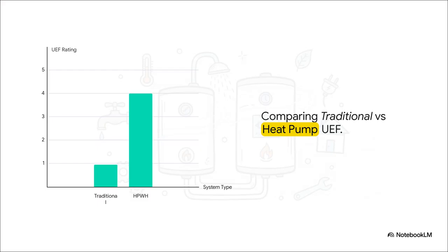Okay, to make that strategic choice, we have to talk about the Uniform Energy Factor, or UEF. It's the gold standard for measuring efficiency, and it brilliantly illustrates the sheer power of multipliers. So traditional electric resistance tanks maxed out at a UEF of about 0.95, meaning they converted 95% of their electrical energy into heat. Not bad, right? But modern heat pump water heaters routinely hit a massive 4.0 UEF. How is that even possible? Well, they don't generate heat from scratch. They just move ambient heat from the air into the water. For every 1 unit of electricity used, you get 4 units of thermal energy. That is an absolute game changer for your ROI.